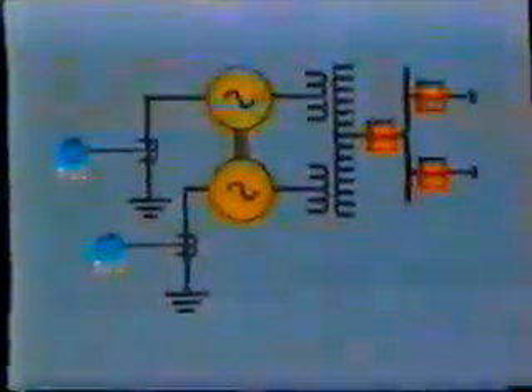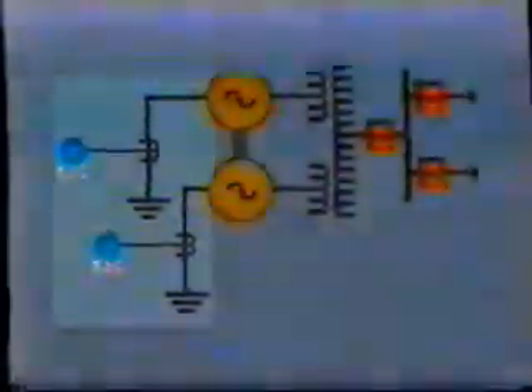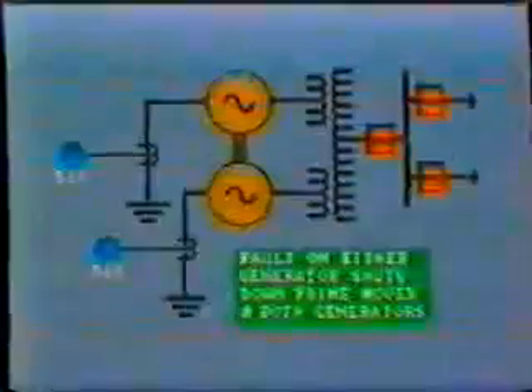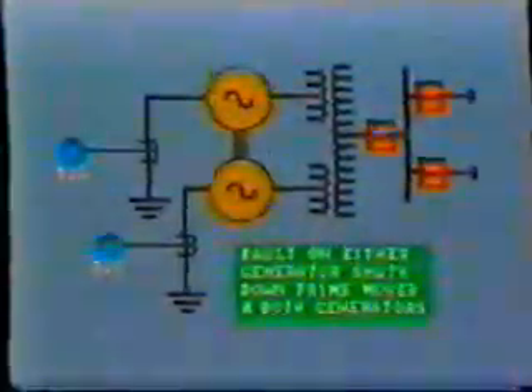In some installations, the generators are connected to two separate delta primaries of a 3-winding transformer. In this case, both generators need to be separately grounded, and each provided with separate primary protection. Of course, a fault on either generator will cause a shutdown of the common prime mover and both generators.